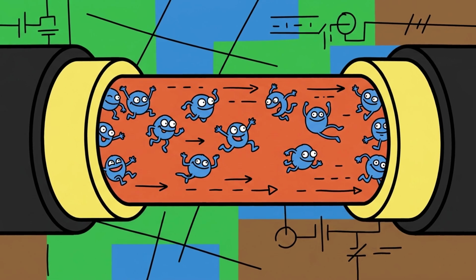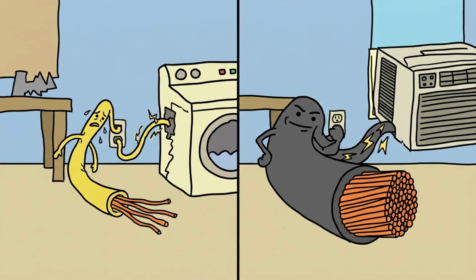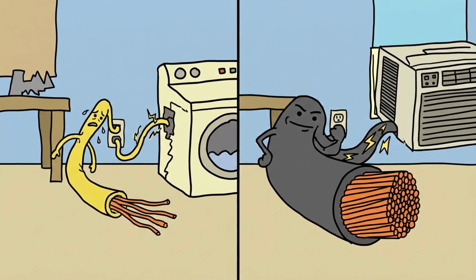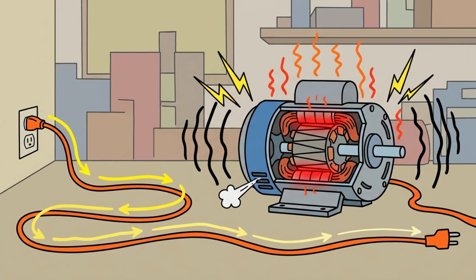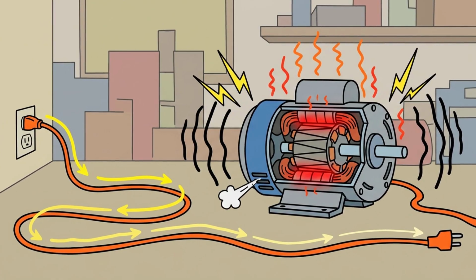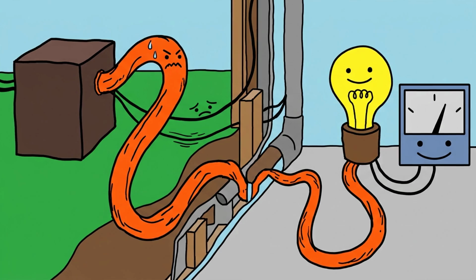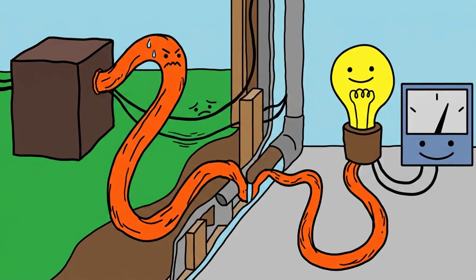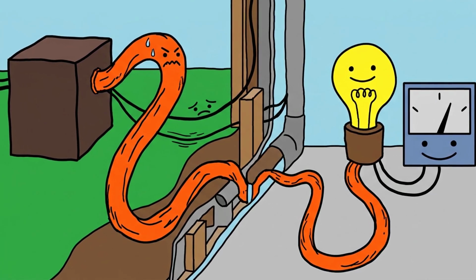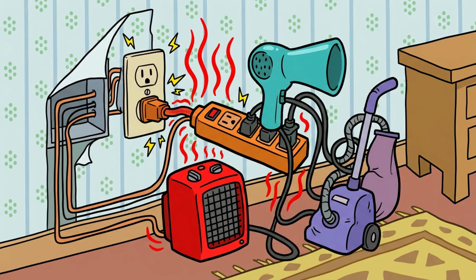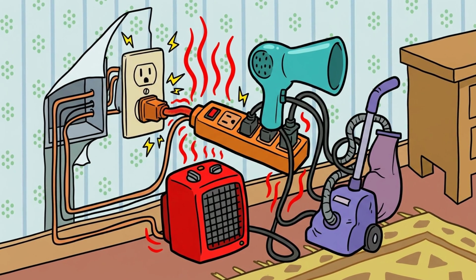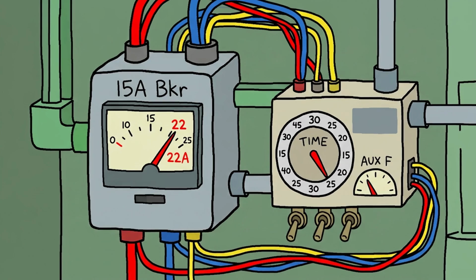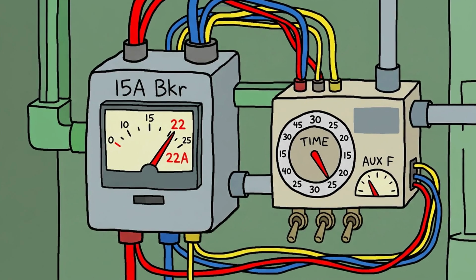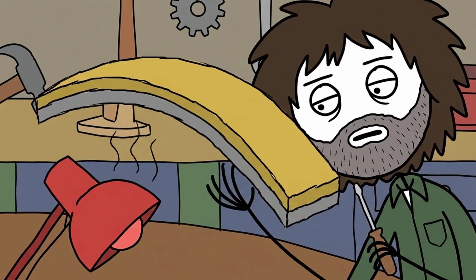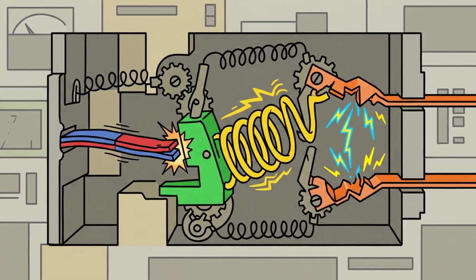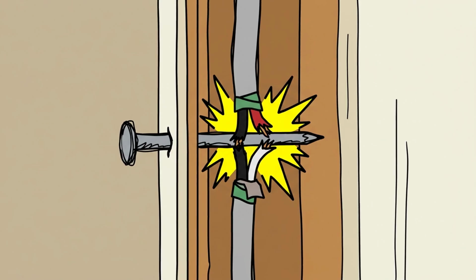The magnetic trip mechanism handles direct short circuits. If a nail pierces a wall stud and bridges hot directly to neutral, resistance drops to near zero. Current spikes instantaneously from 15 amps to over 500 amps in a millisecond. Waiting for a bimetallic strip to bend during a 500 amp fault would cause an immediate explosion of sparks and melted copper. To combat this, short circuit current passes through a compact electromagnetic coil wrapped around an internal plunger. The sudden surge of massive current generates an intense magnetic field, violently pulling the plunger forward. The plunger strikes the trip latch in under 10 milliseconds, popping the breaker open before copper wire melts.